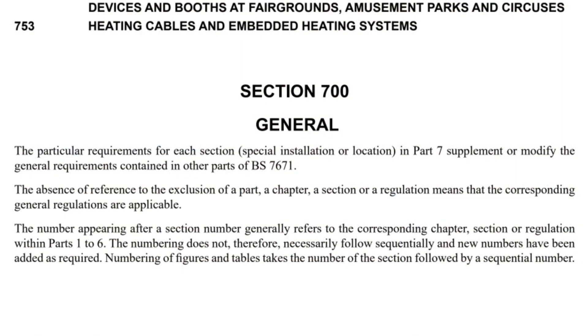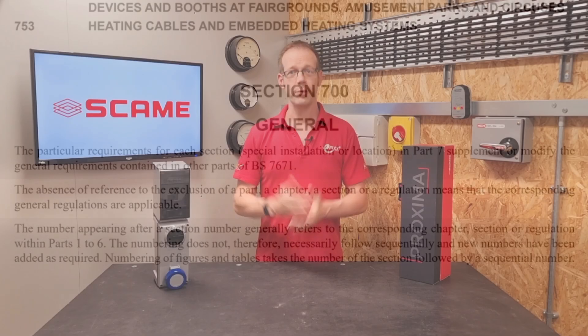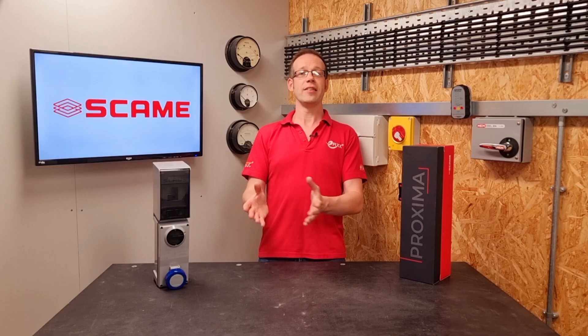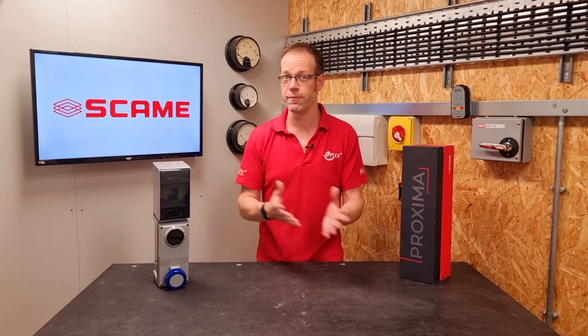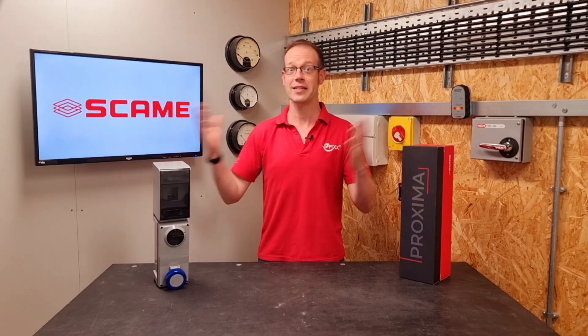Or is it? Reading on: the absence of reference to the exclusion of a part, a chapter, a section or a regulation means that the corresponding general regulations are applicable. So because the regulation on EV charge point connectors doesn't specifically exclude Regulation 553.1.201, then it must be applicable — so a BS EN 60309 socket outlet isn't acceptable.